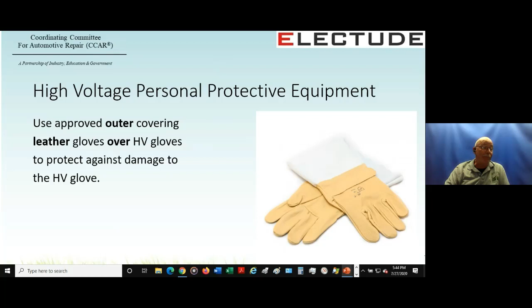If I was doing this in person, I would have samples of PPE to pass out among the group. Unfortunately, the photo is going to have to suffice. And there you see the Salisbury label. It is rated as class 0 up to 1000 volts AC. And also notice that they have expired long ago. We got them and they were 7 months expired when we took them out of the box.